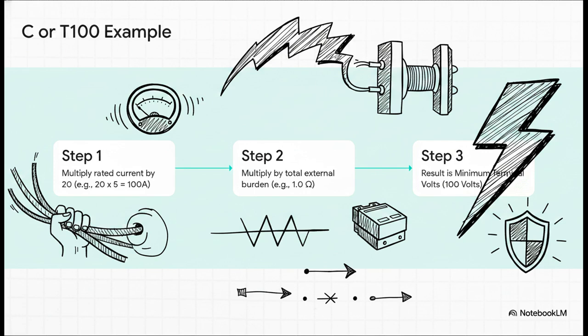Let's walk through the exact calculation. Step 1. Multiply your rated secondary current, which is usually 5 amps, by 20. That gives us 100 amps. Step 2. Multiply that by your total external burden. For this example, let's just say it's 1.0 ohm. Step 3, the result is 100 volts. And there you go, that is exactly what C100 means. This math just ensures your relay has enough voltage to push that massive current through the wire during a worst-case fault condition, all without exceeding a 10% ratio error.